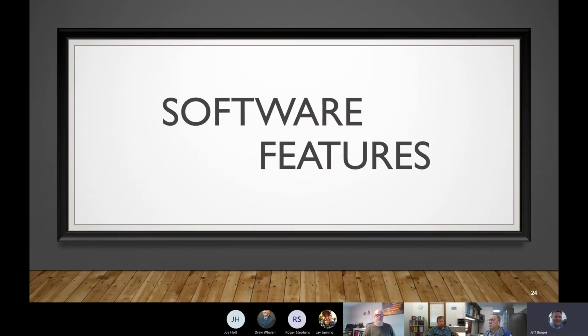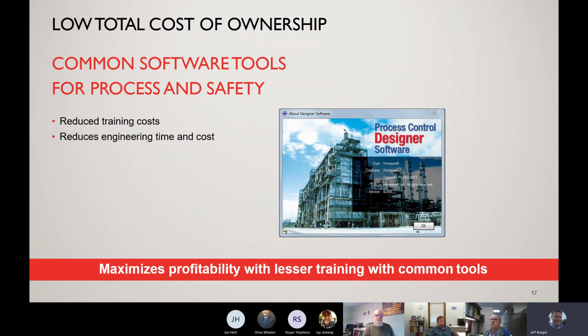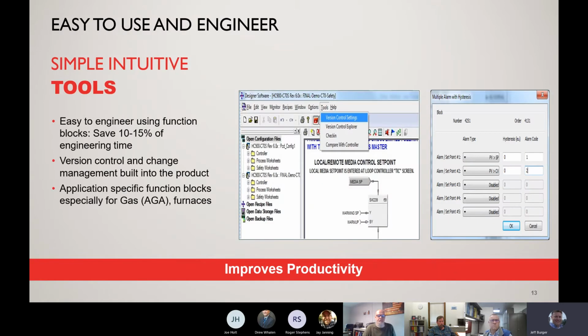Let's talk a little bit about the software that's used to configure the HC900. The nice thing is on this software, it's one common software tool that's used for both process and safety configuration. So it'll help reduce training costs when using the HC900. It also reduces a lot of engineering time and cost as well. The HC900 tool, we've heard from customers that it's able to reduce engineering time by 10 to 15% using this one common platform that is used to not only configure the safety I/O, but your process control, your discrete control. It's all offered under one software package.